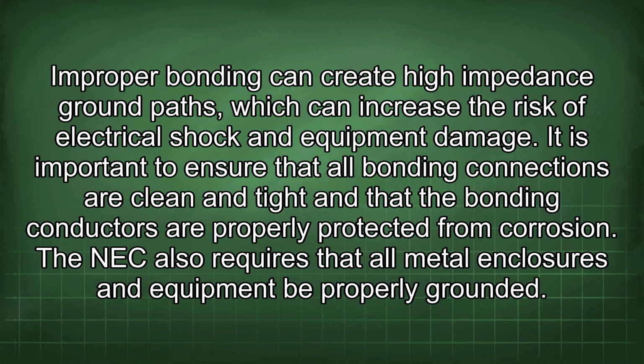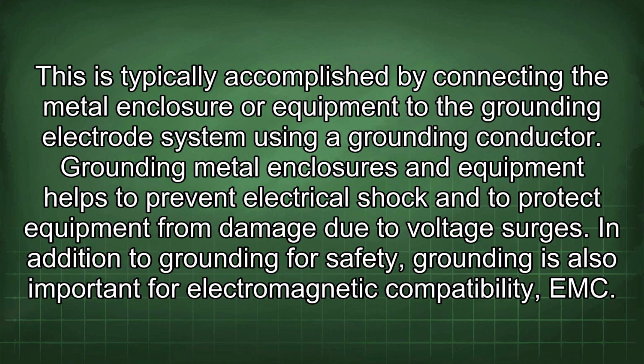It is important to ensure that all bonding connections are clean and tight and that the bonding conductors are properly protected from corrosion. The NEC also requires that all metal enclosures and equipment be properly grounded. This is typically accomplished by connecting the metal enclosure or equipment to the grounding electrode system using a grounding conductor. Grounding metal enclosures and equipment helps to prevent electrical shock and to protect equipment from damage due to voltage surges.